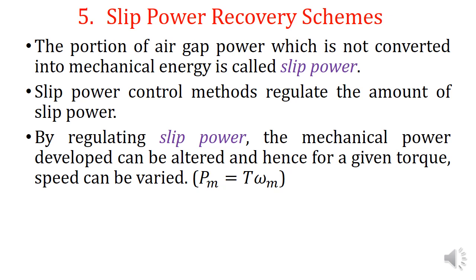The air gap power is equal to mechanical power plus slip power. So if we are controlling or varying the amount of slip power, we are varying the amount of mechanical power. Since Pm = T × ωm, for a given torque, if we are controlling Pm, then speed can be controlled.